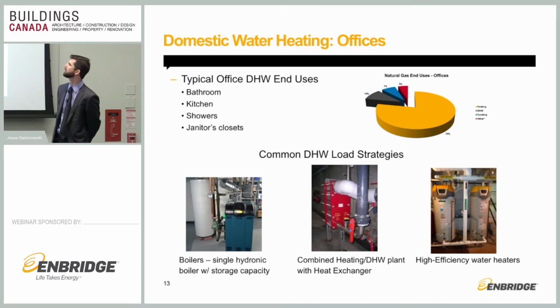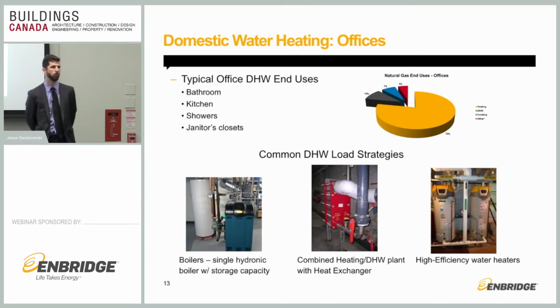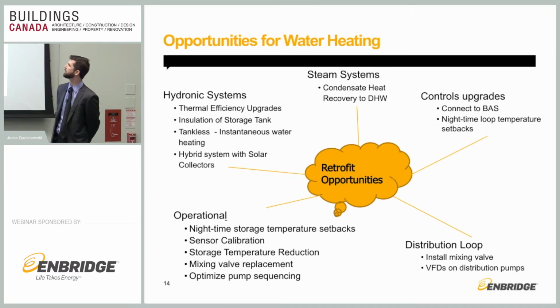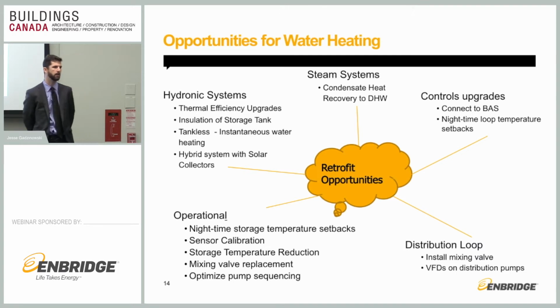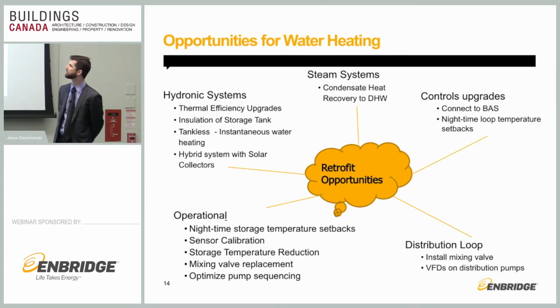Typical office domestic hot water end uses are bathrooms, kitchens, showers, and janitors' closets. What we're seeing mostly for supplying heat to these loops is single hydronic boilers with storage capacity, or maybe a combined heating and domestic hot water plant with a heat exchanger, or even just high efficiency water heaters, which is more common, I'd say. Next, please, Zig. So similar to the heating side, for hydronic systems in the top left, you're looking at just boiler upgrades, getting your thermal efficiency as high as possible, insulating the storage tanks, instantaneous hot water heating.